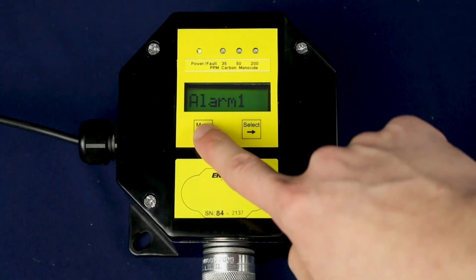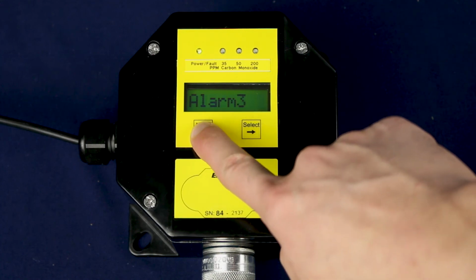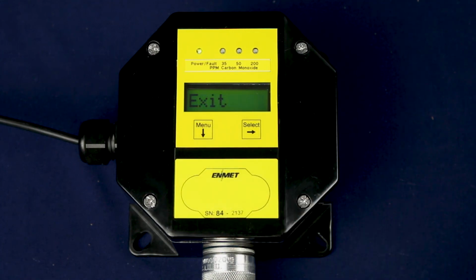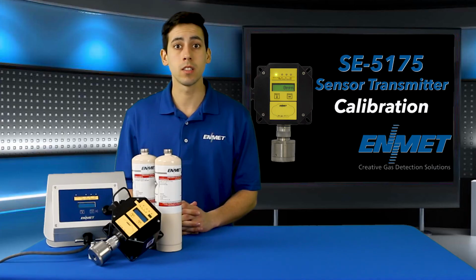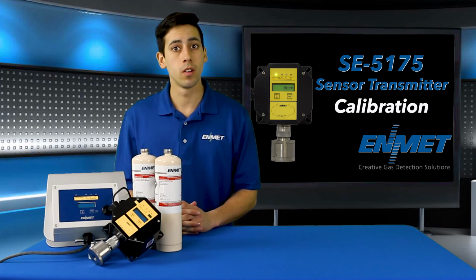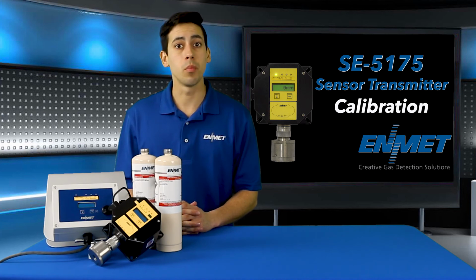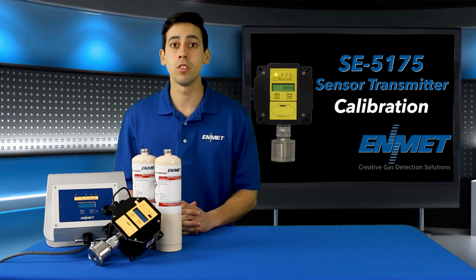Press the menu key to cycle through the maintenance menu options until you see Exit displayed. Then, press the Select key to exit the maintenance menu and return to the operational mode. This completes the calibration of ENMET's SE-5175 sensor transmitter.